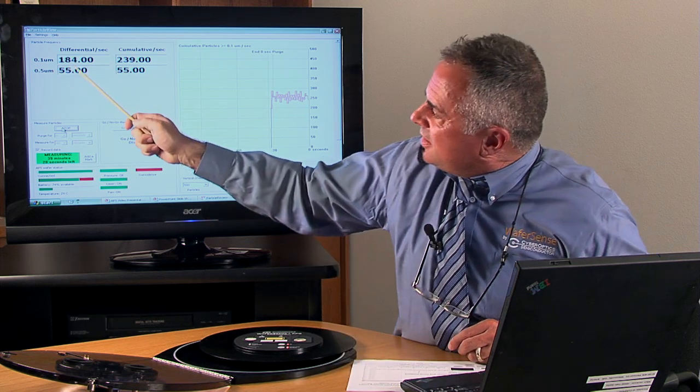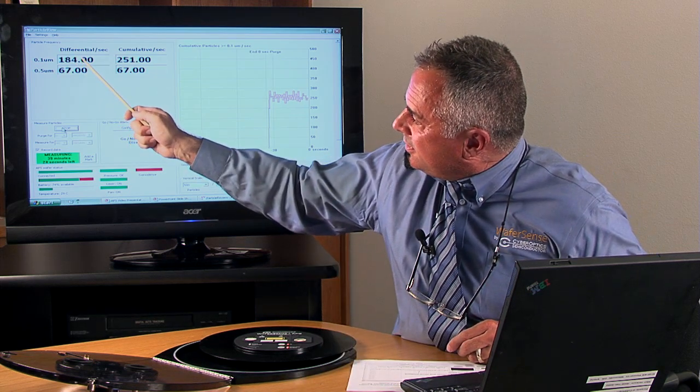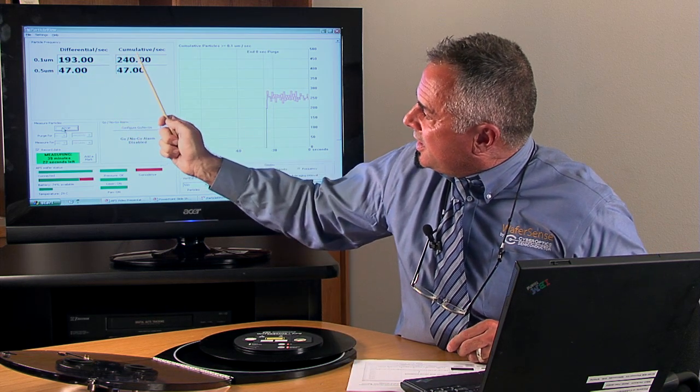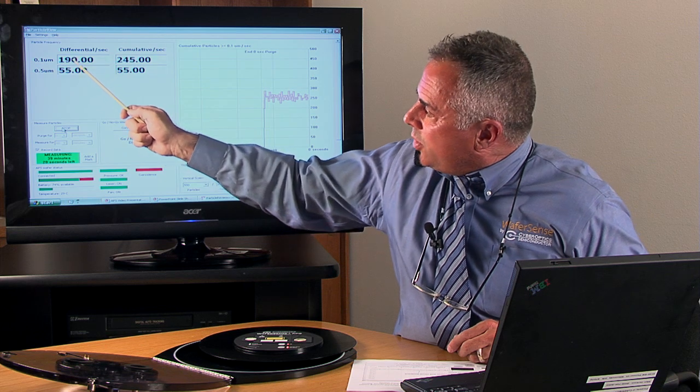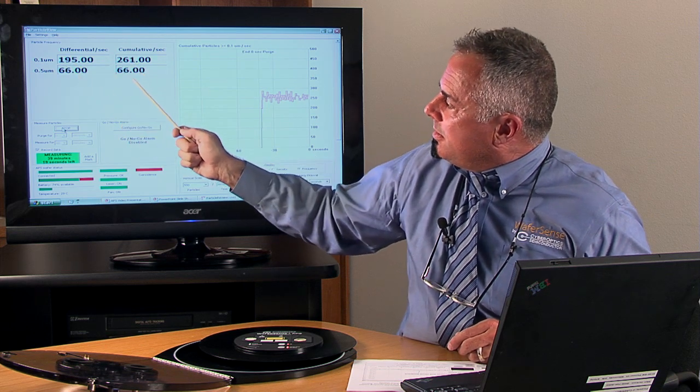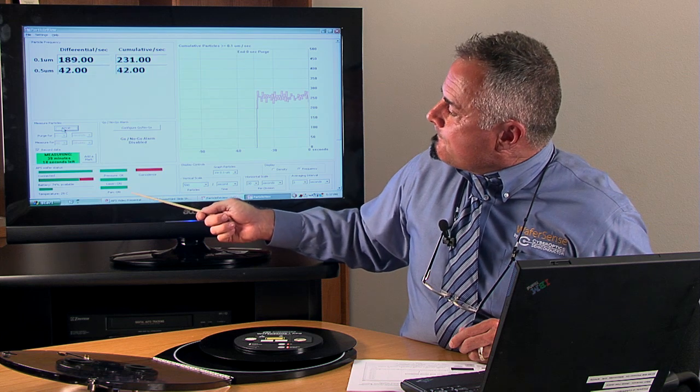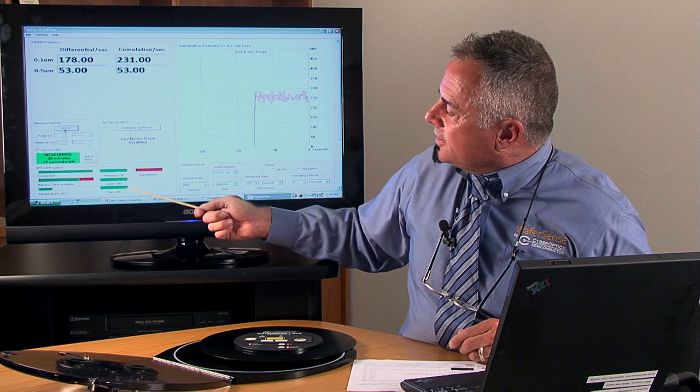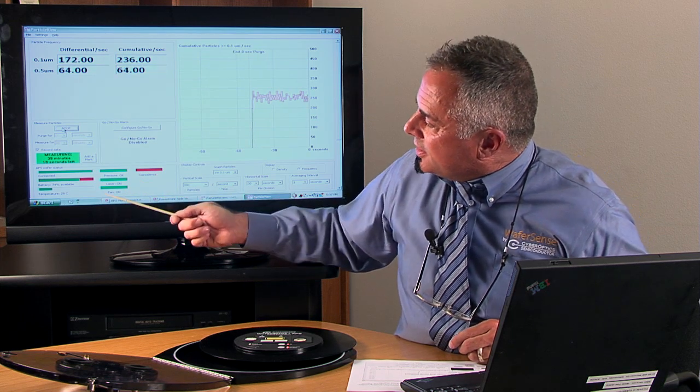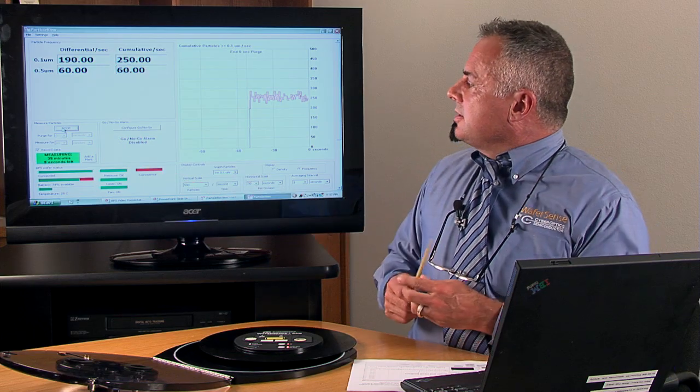Over here, you will see our differential and cumulative counts in both the 0.1 and 0.5 micron bins. So we have some indicators here, pressure, laser, fan, coincidence alarms, battery status, etc.